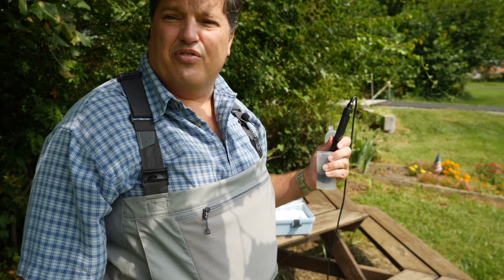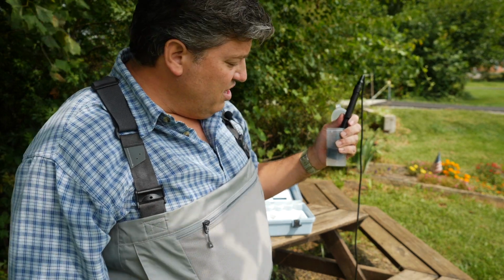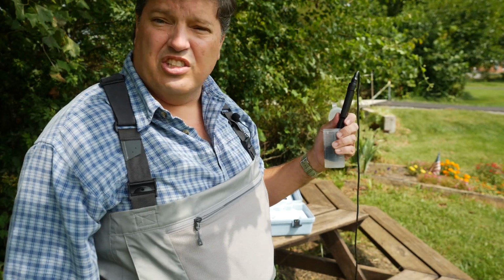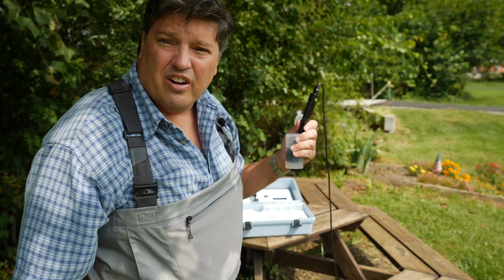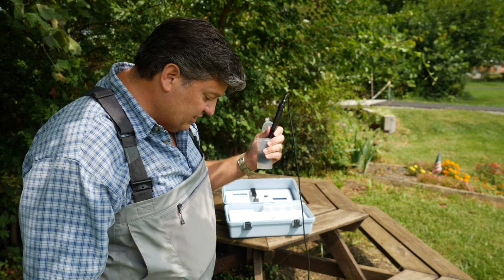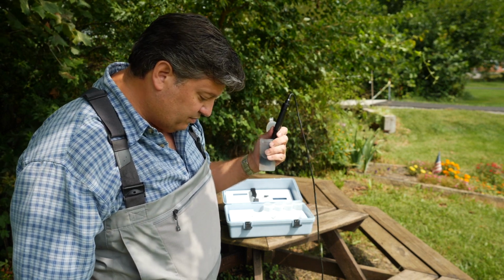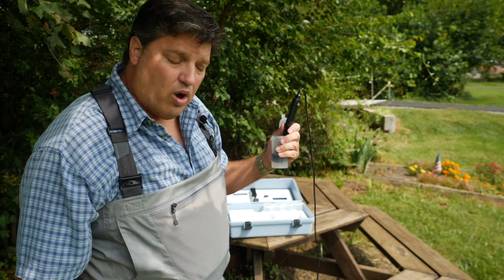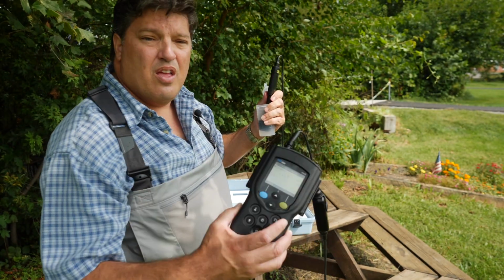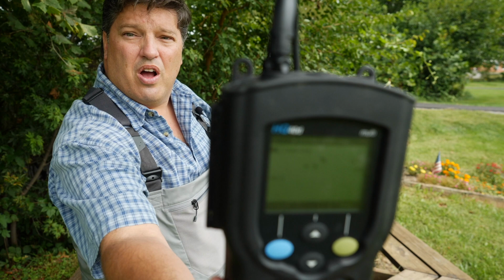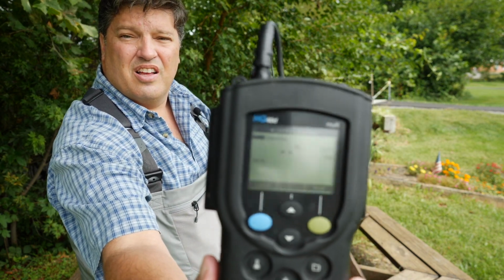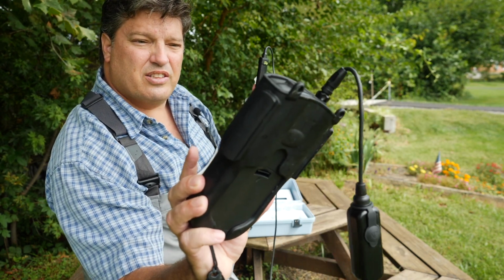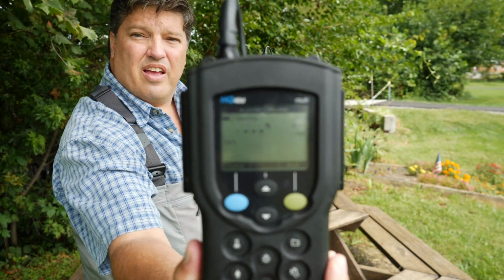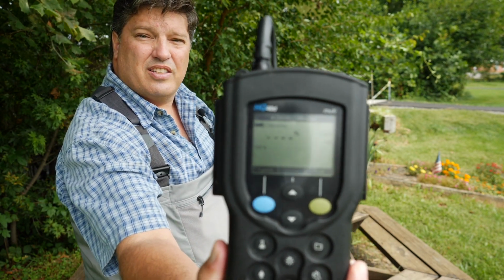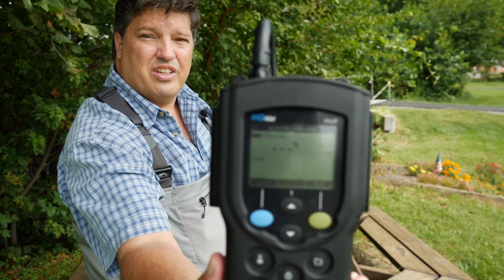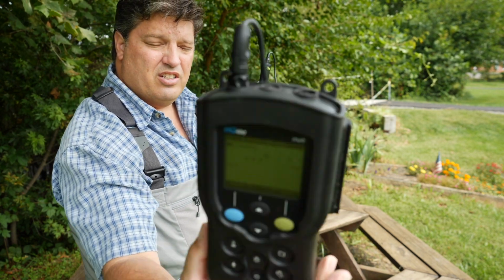It may take a few minutes for it to stabilize. I'm gently shaking the probe a little bit to make sure that oxygen stays mixed in with the water as it goes through the stabilization process. This probe also measures water temperature, if you can see on the screen there. The temperature today looks like it's about 22.4. And I'm not sure if you can see on the screen, but the process is stabilizing. So we're getting close to the point where it's calibrated here.